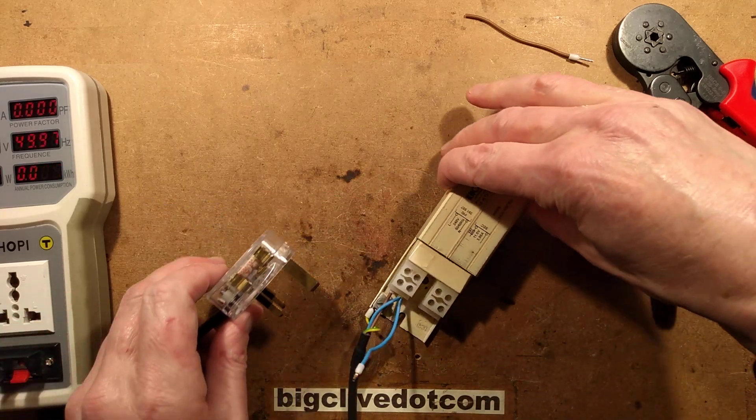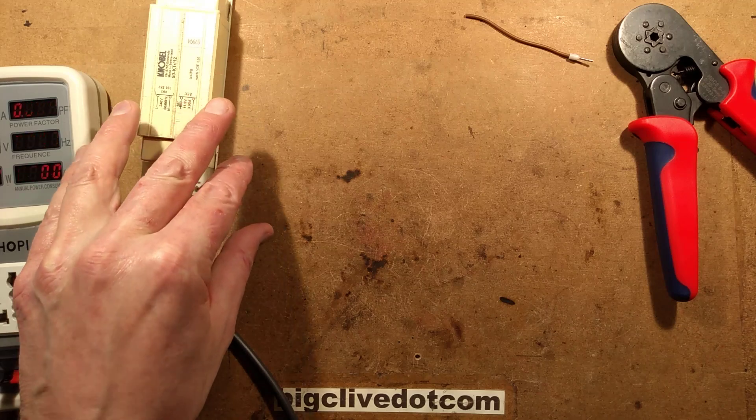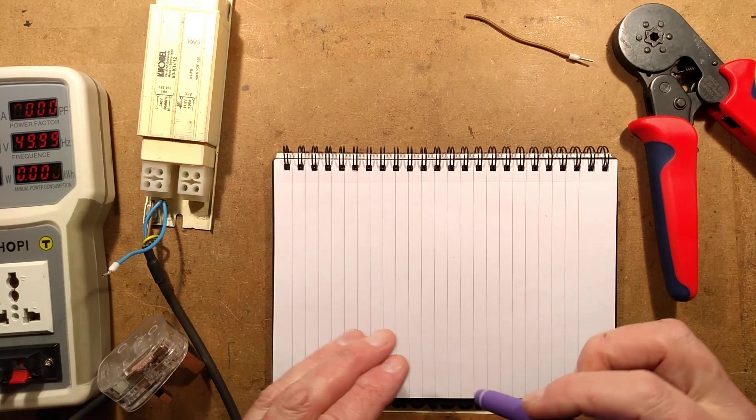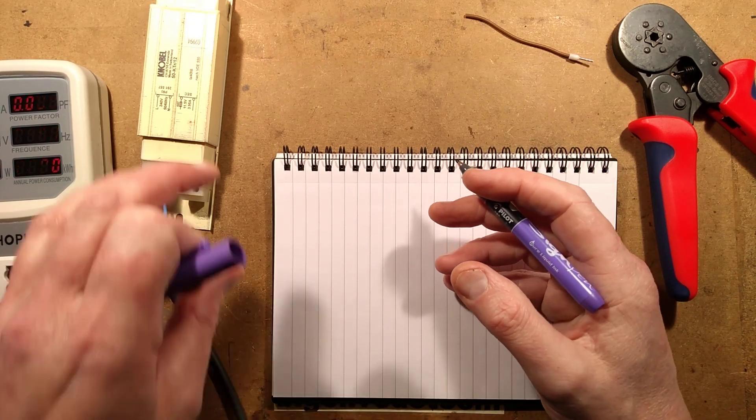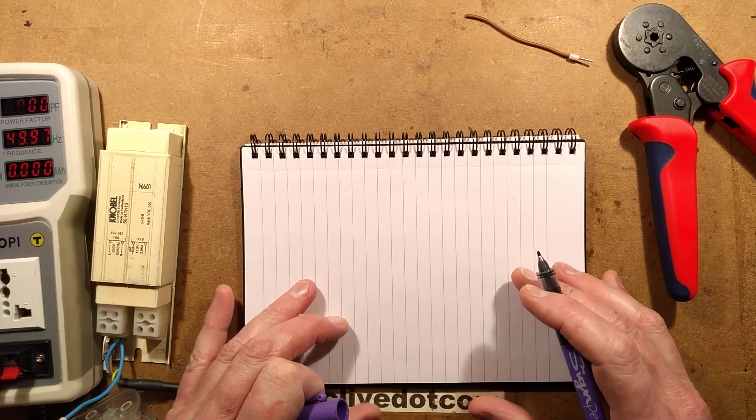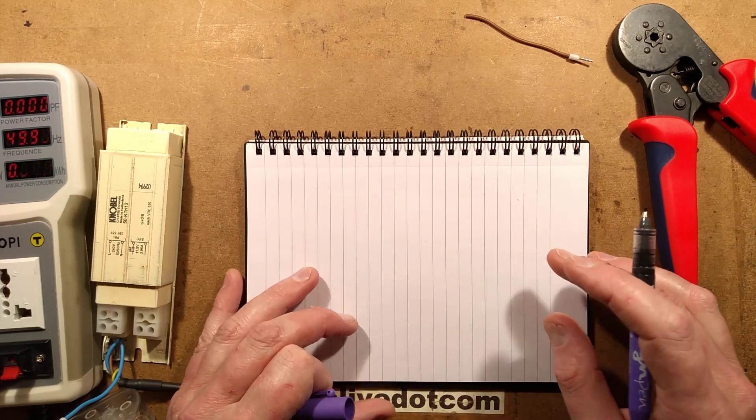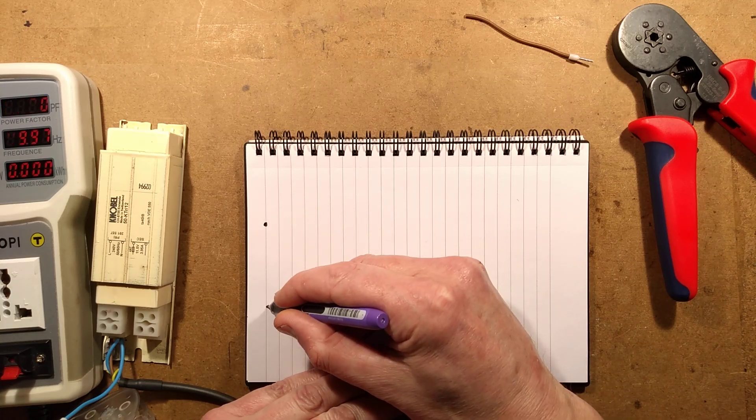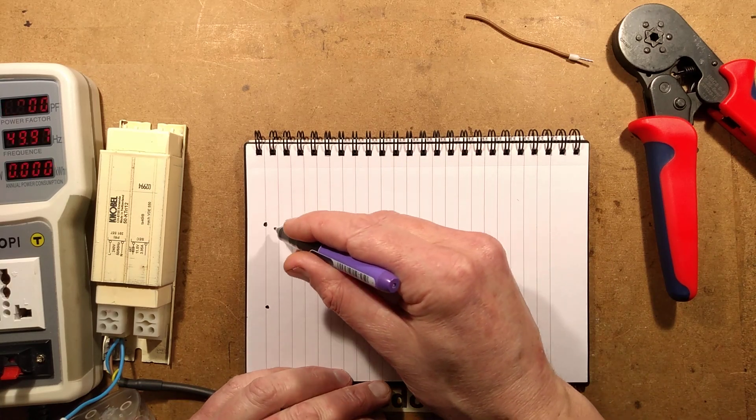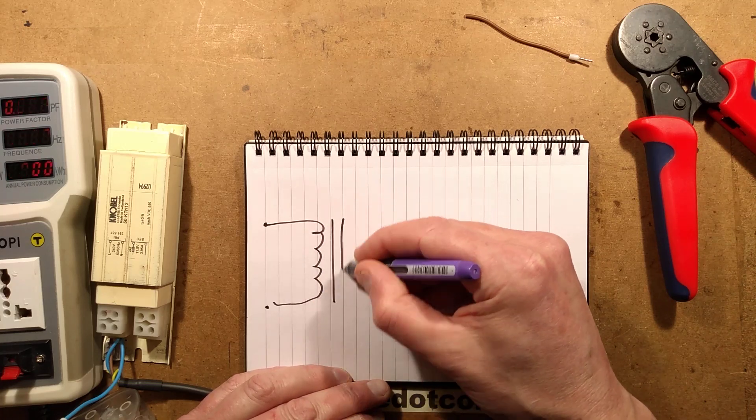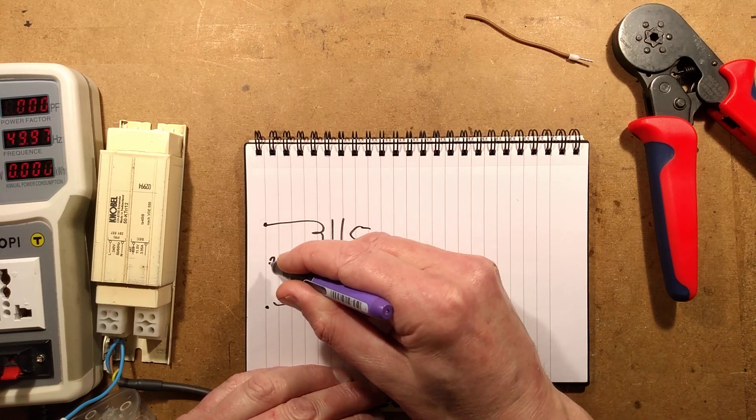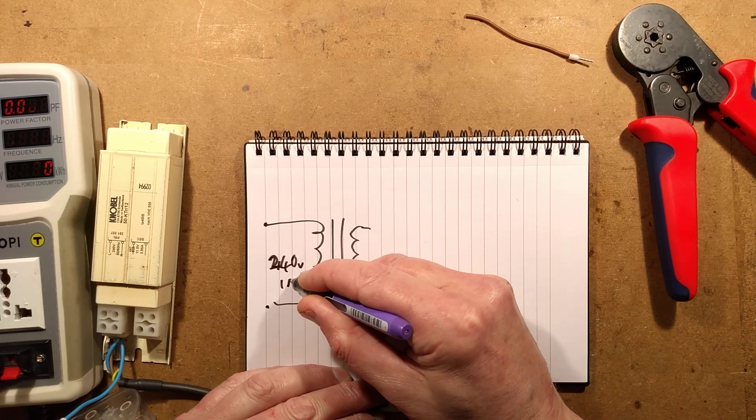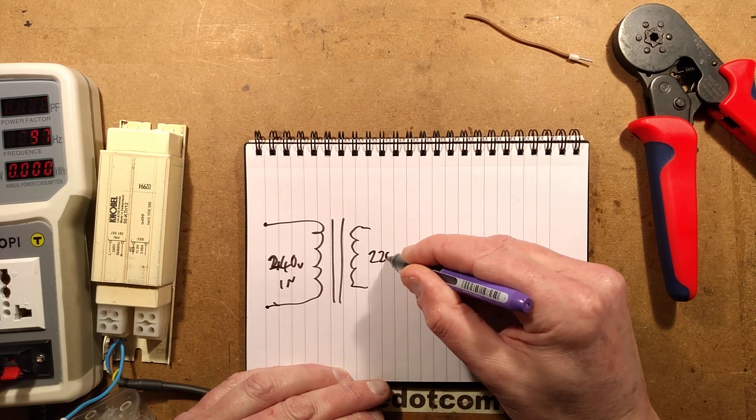So getting on to this, let's bring the notepad in and I'll show you what I'm going to do. So imagine you've got a piece of industrial equipment and it's rated for 220 volts, but you're giving it 240 volts and you want to drop the voltage to it because it is causing problems. If you had a transformer, you could bring in a traditional transformer with a 240 volt winding, fully isolated, and you could have the 240 in the primary and you could have a 220 volt out.